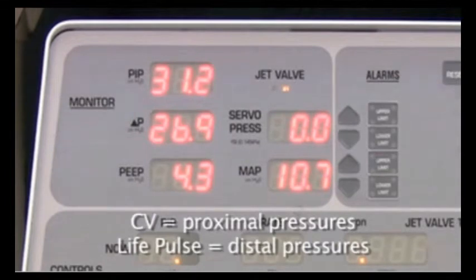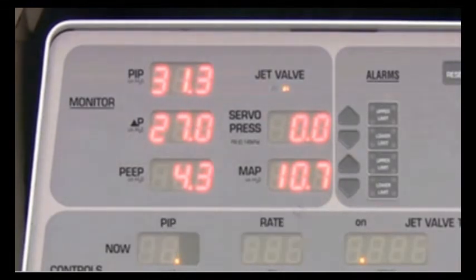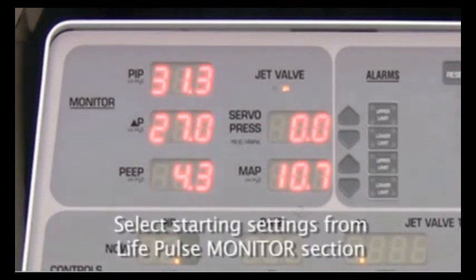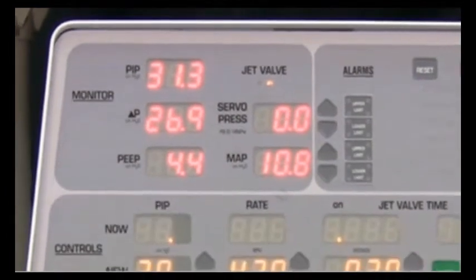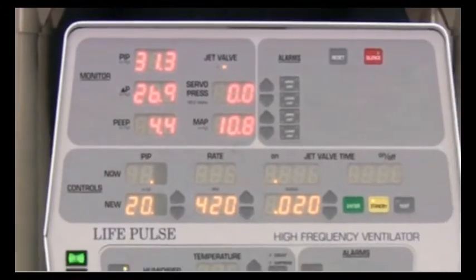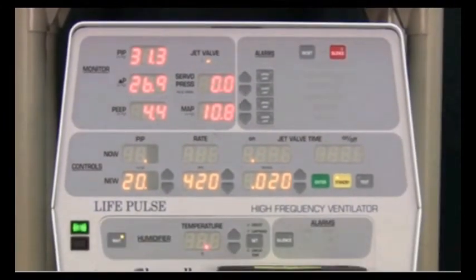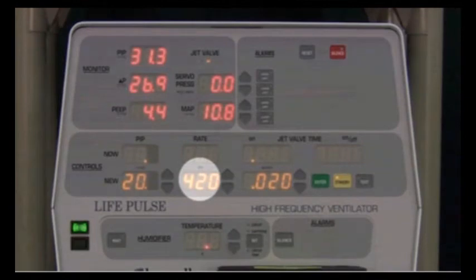Remember that the conventional ventilator displays pressures measured proximally, while the LifePulse displays approximations of distal tip pressures. We recommend that the startup decisions be based on the pressures displayed in the LifePulse monitor section. The PIP setting chosen for initiation of high-frequency ventilation will really depend on the PIP currently being monitored by the LifePulse in its standby mode. The other initial high-frequency settings are usually left at the default values, which are a rate of 420 breaths per minute and an on-time or inspiratory time of 0.02 seconds.